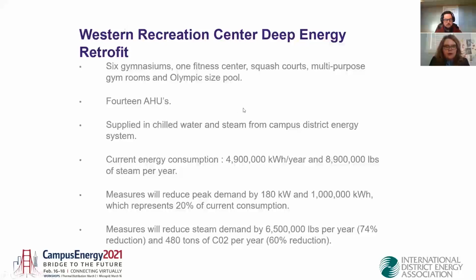And here we have the rec center. So we have 6 gymnasiums, a fitness center, squash courts, a swimming pool, and a lot of AHUs. So here again, we're installing local heat pumps to produce not chilled water, but heating water. So that represents about 8.9 million pounds of steam that the building is currently consuming, and we're going to reduce it by 6.5 million pounds of steam per year. So it's about a 74% reduction. And we're going to reduce the CO2 emission by 480 tons. So that's about a 60% reduction.